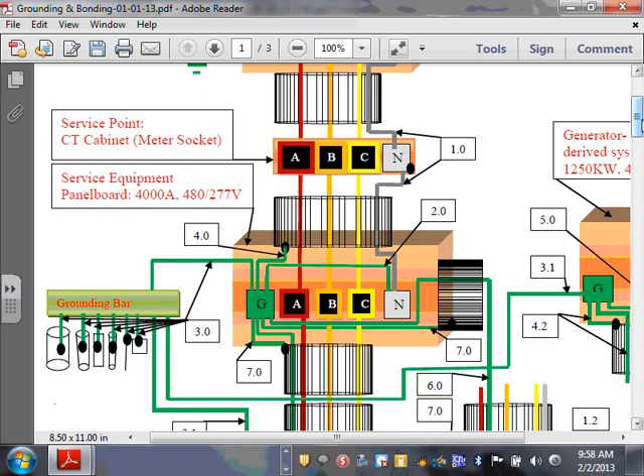In the high voltage, guys, you'll be shocked if you know what happens with a non-metallic object in, say, a 69,000 volt system. The non-metallic accumulates charges, right? And what happens if you get zapped by a big charge from a 69,000 volt system? You get killed. So sometimes they connect and drain the non-metallic just to drain the charges from it. So there are other issues. Luckily, at 600 volts or less, we don't have to worry about that. So we don't ground the PVC.